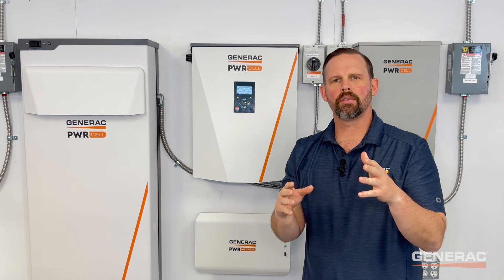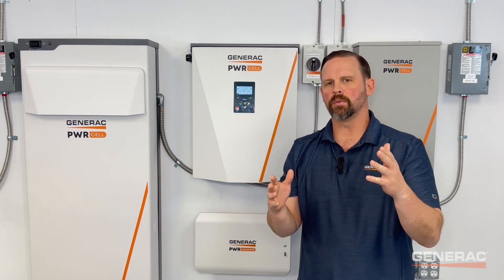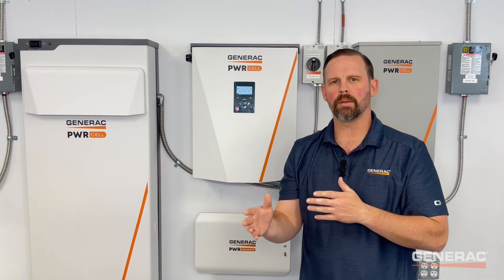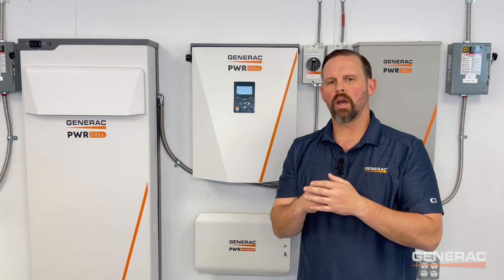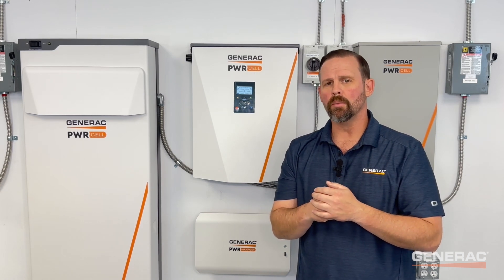If reset does not resolve your issue or if cell imbalance returns, verify there are no environmental factors that would lead to a severe temperature imbalance between modules. For example, an external heat source such as a space heater may cause a cell imbalance due to temperature. Remove the heat source, and the issue should correct itself.